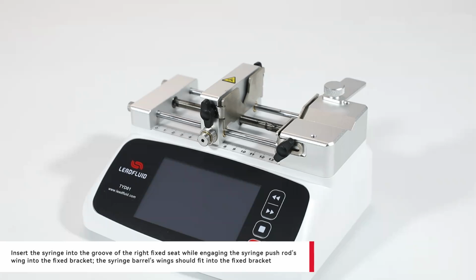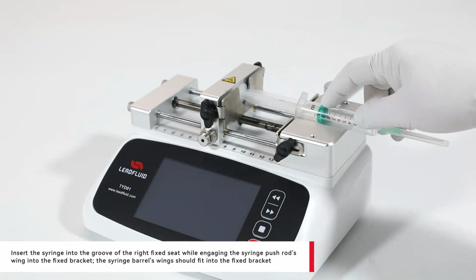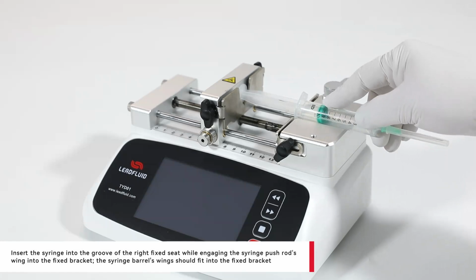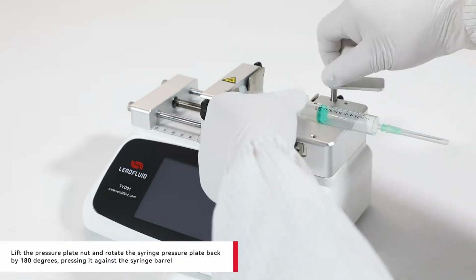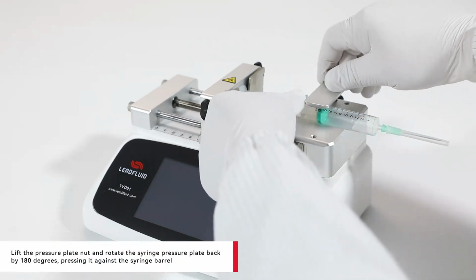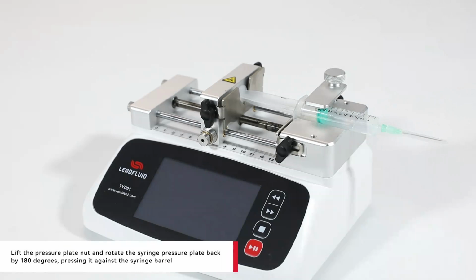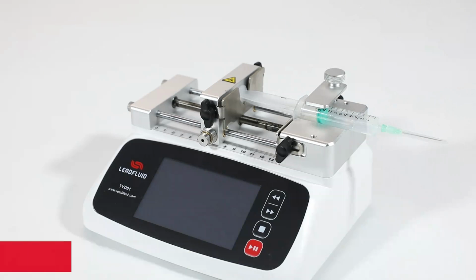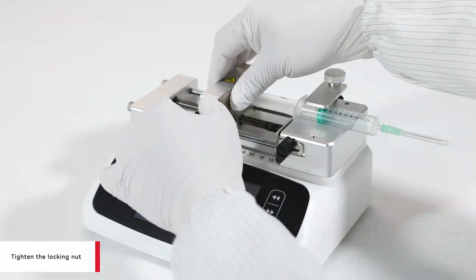Insert the syringe into the groove of the right fixed seat while engaging the syringe push rods. Wing into the fixed bracket. The syringe barrel's wings should fit into the fixed bracket. Lift the pressure plate nut and rotate the syringe pressure plate back by 180 degrees, pressing it against the syringe barrel. Tighten the locking nut.